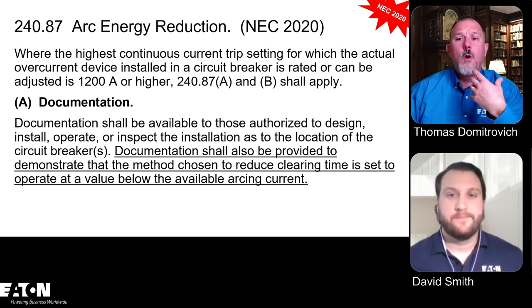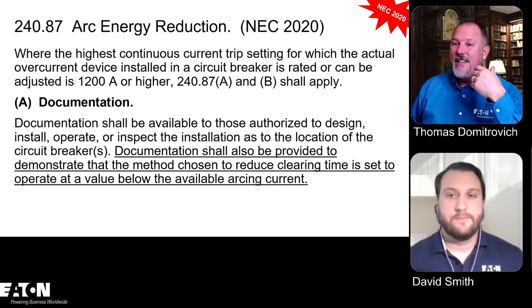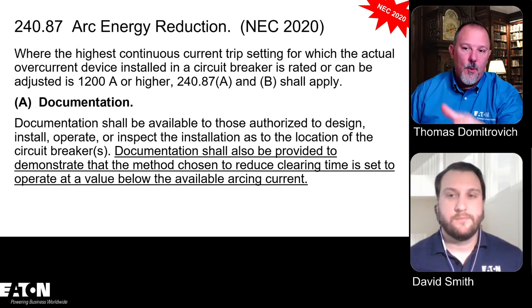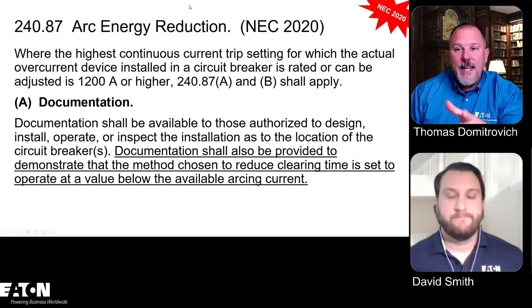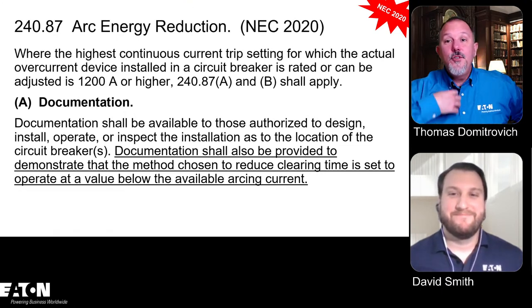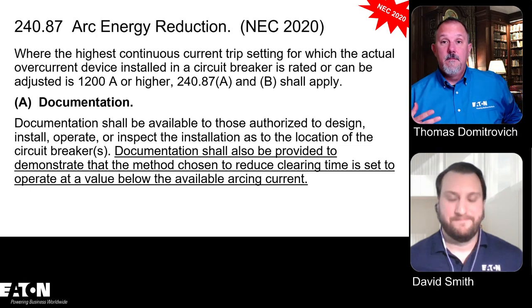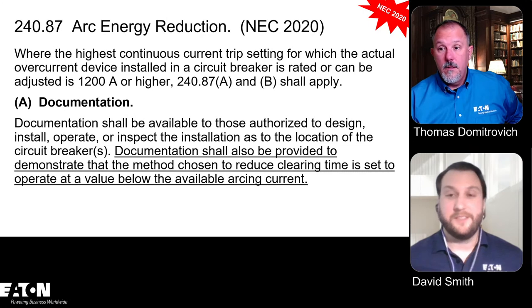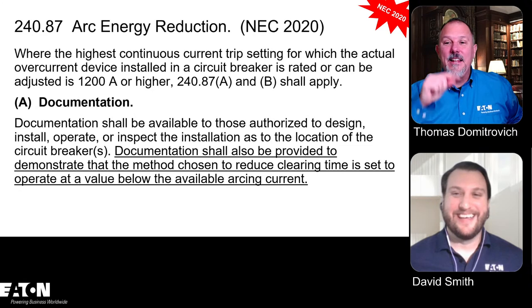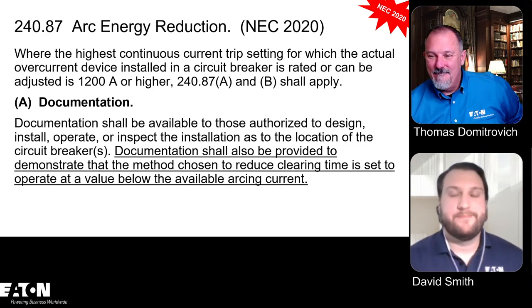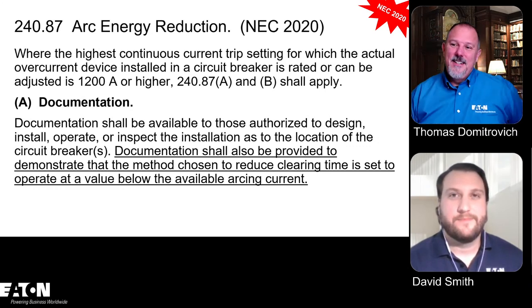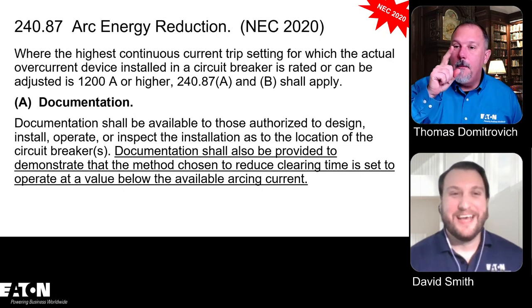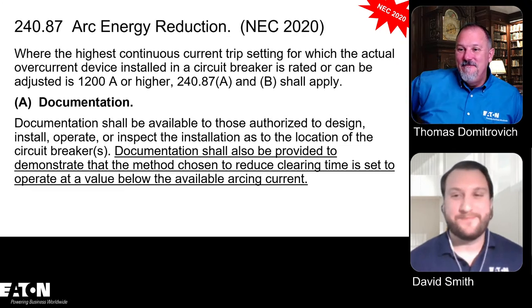Yep. So what we can do, though, is we can say, look, the arcing current has to be in the instantaneous region, it has to activate one of these technologies. And so in the 2020 cycle, they were very clear to add that sentence: documentation shall be provided to demonstrate that whatever you choose out of the list that they give you, it has to activate. But they don't say minimum arcing current, David. So if I use the maximum arcing current because it saved me money, would I be technically wrong? Yes, technically. Would I be violating the National Electrical Code? It depends. It doesn't say the maximum arcing current or minimum arcing current. Yeah, that's true. It says the available arcing current.